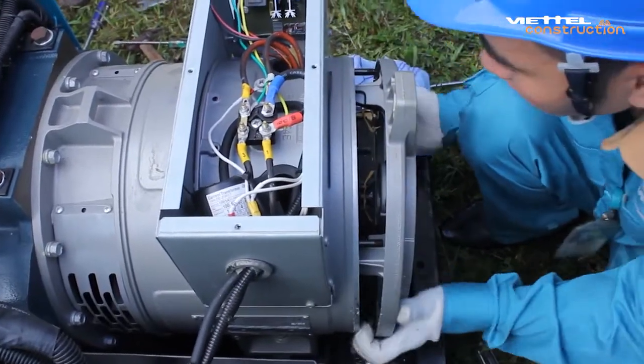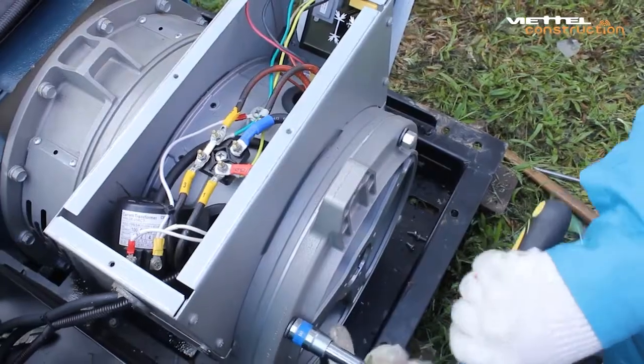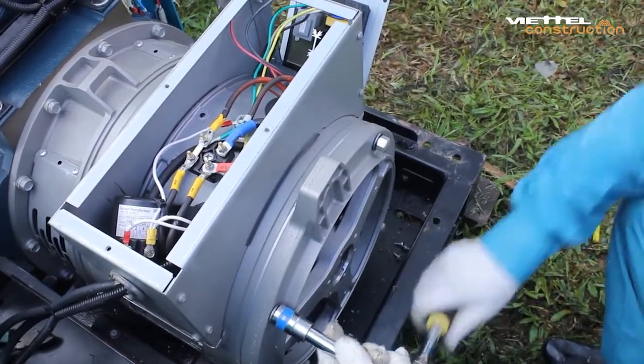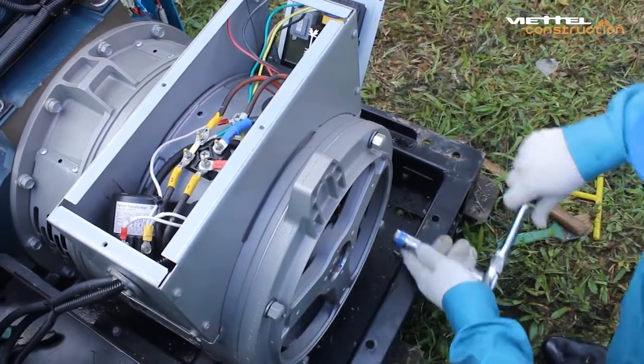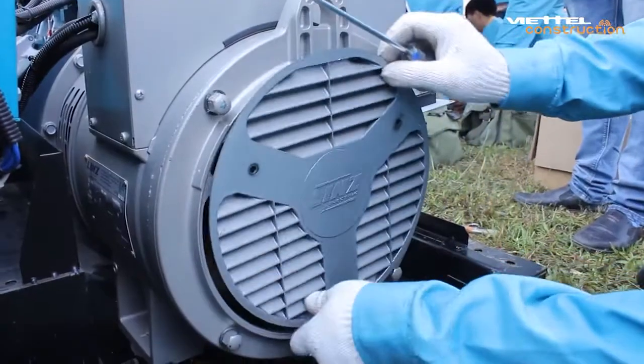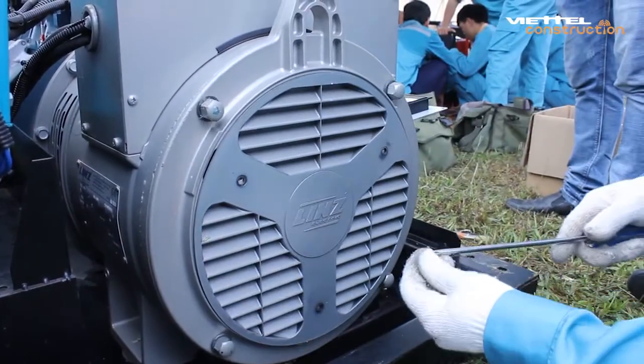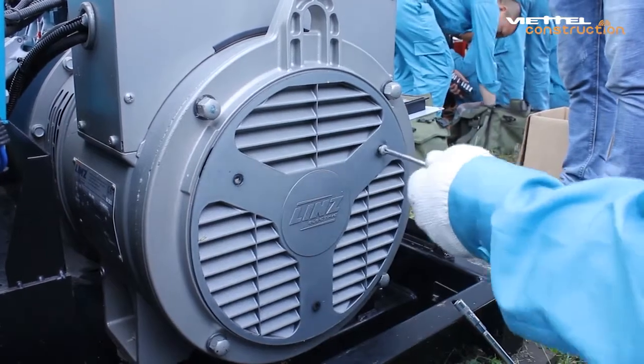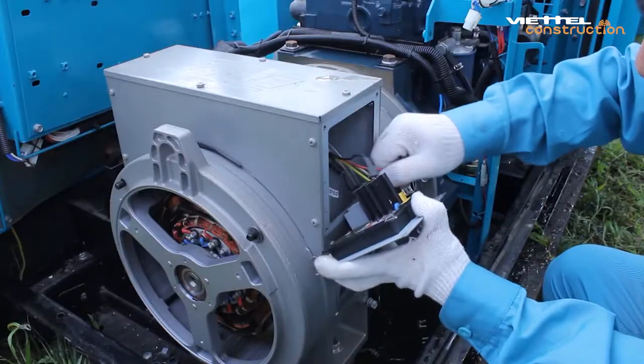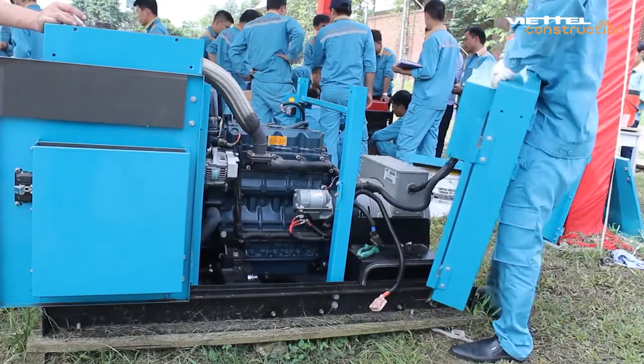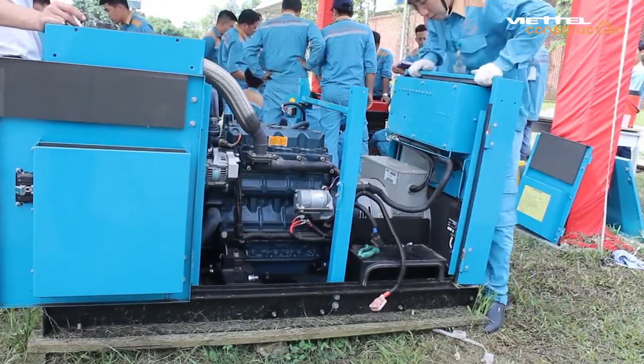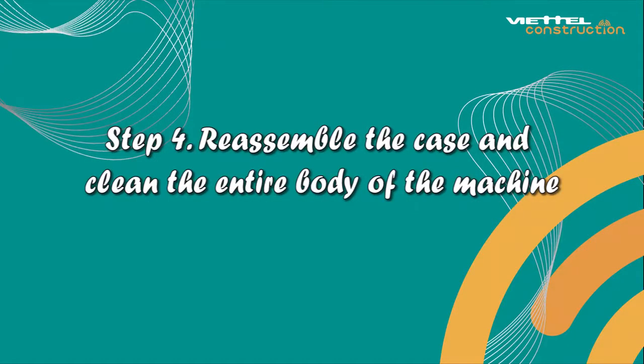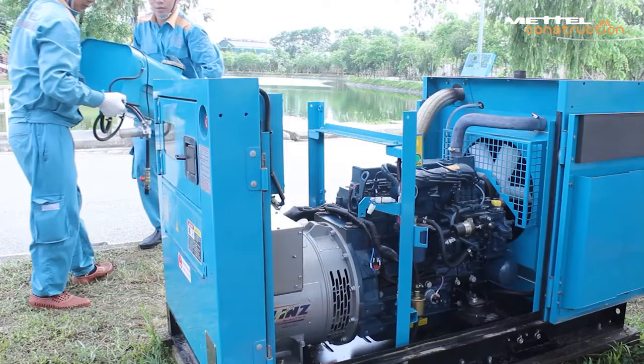Reassemble the protective cap. Tighten the bolt positions. Reassemble the excitation wire into the AVR board. Reassemble the dashboard surface of the generator. Step 4. Reassemble the case and clean the entire body of the machine. Reinsert the oil tank.